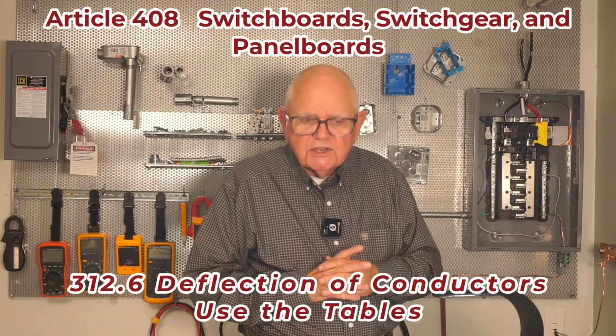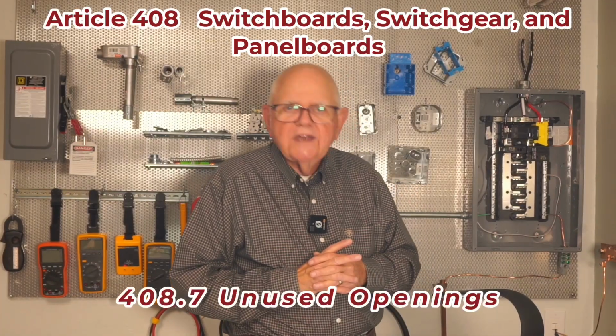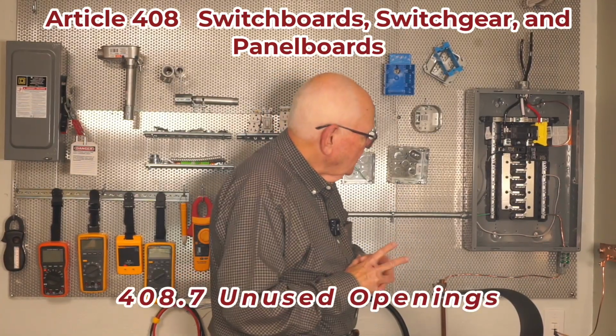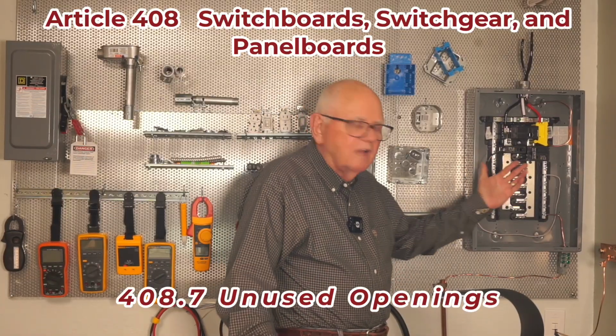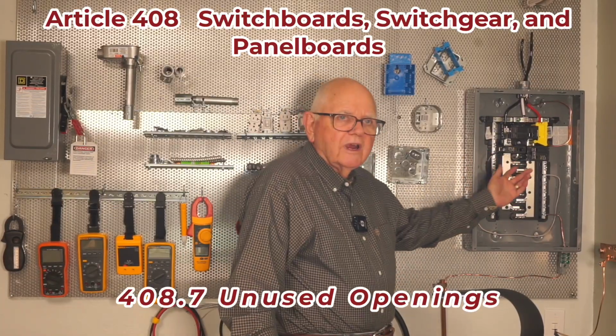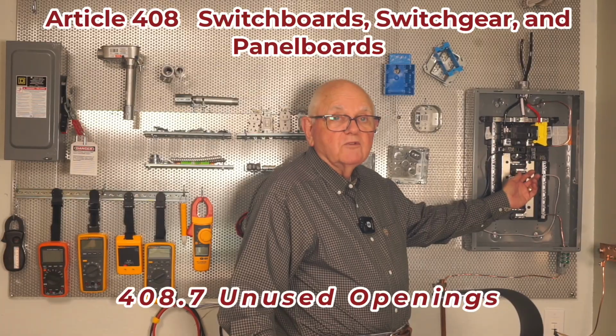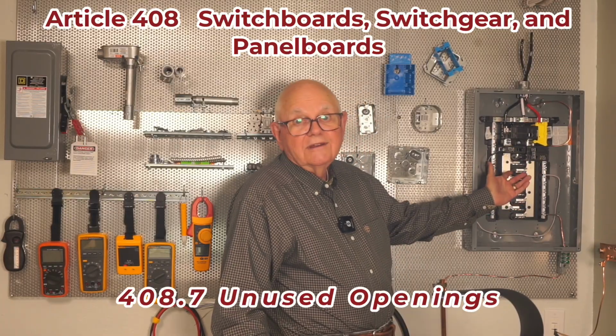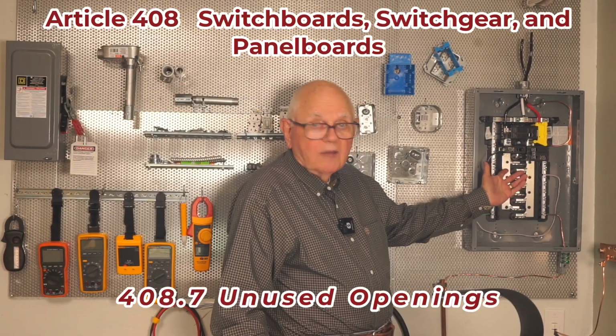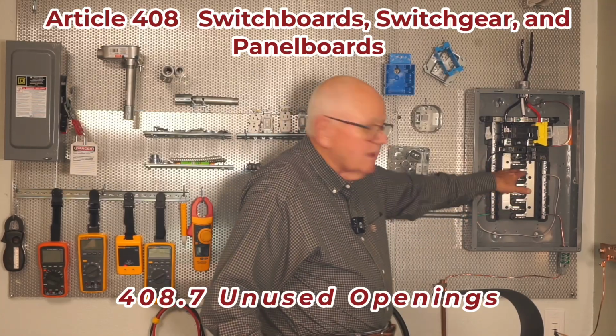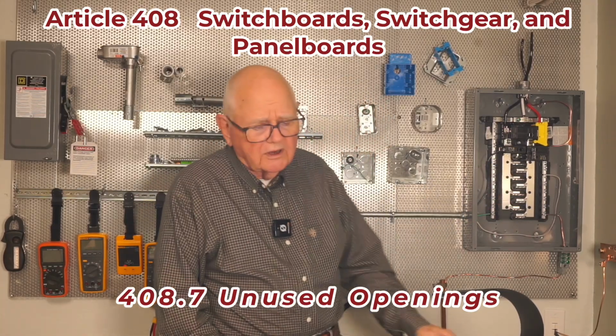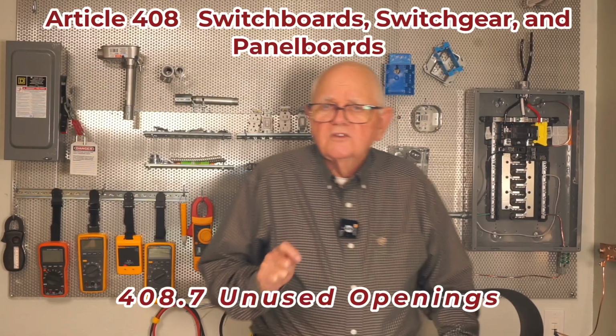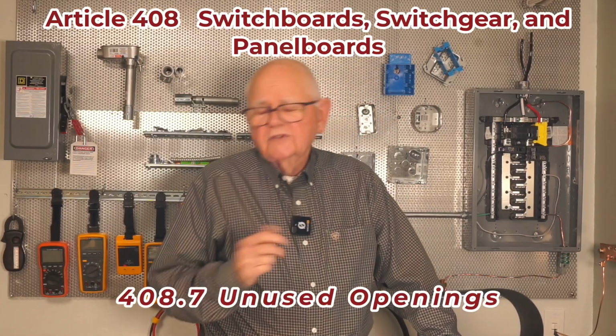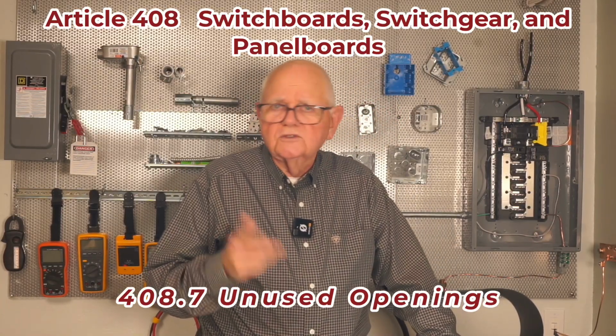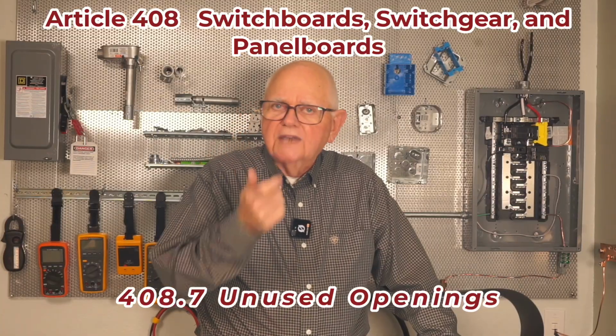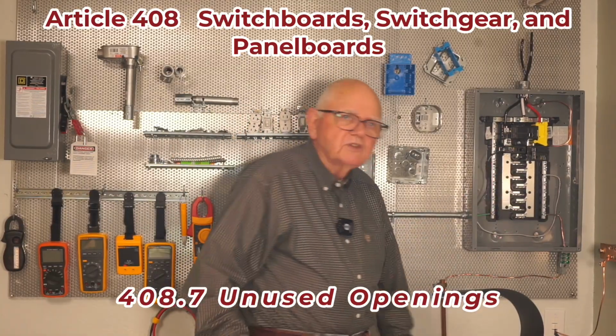Another issue is closures. Article 408 says I must have closures. So for instance, and I know you've seen it all the time, you see on a panel board where a circuit breaker has been removed and you've got a hole now, and a slot, an empty slot. And so I could go in and easily stick my finger in there and contact some live bus work. Obviously very dangerous. So I have to use an identified closure. You have to go to the manufacturer for your panel board, right? Because those are the ones that'll fit. And you get those little plastic closures and you snap them in place over those spots.